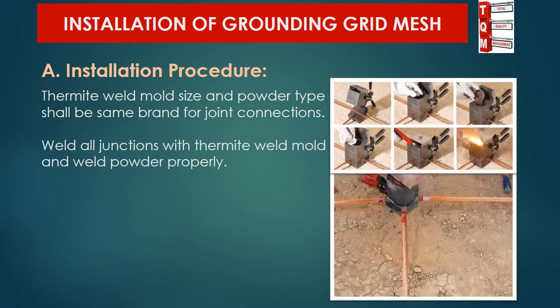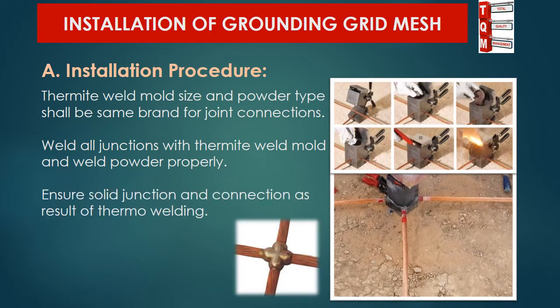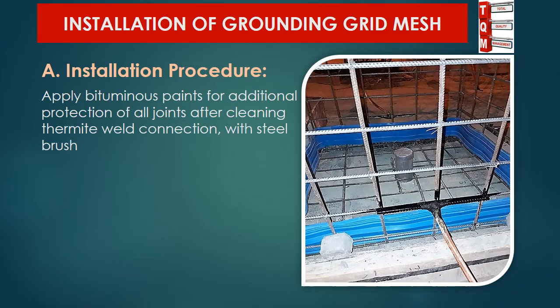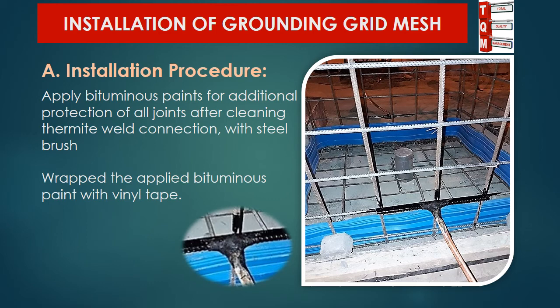Weld all junctions with thermite weld mold and weld powder properly, ensuring a solid junction and connection as a result of thermal welding. After performing the joint welding, it is very important to clean the thermite weld connection with a steel brush, then carefully apply bituminous paint for additional protection of the joints, and then wrap the applied bituminous paint with vinyl tape.